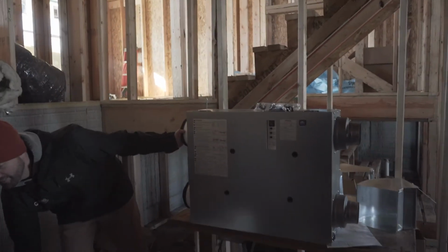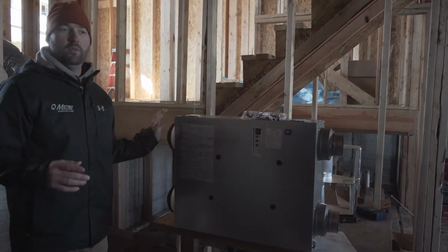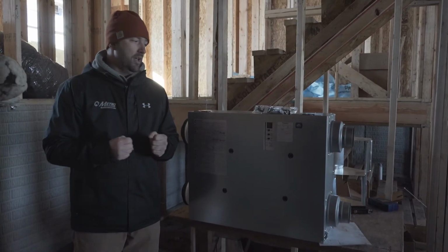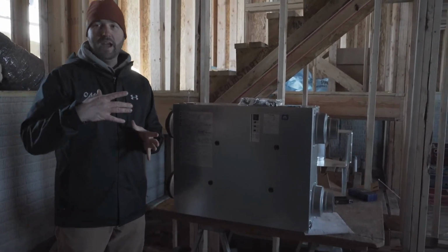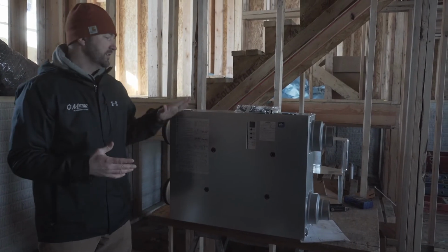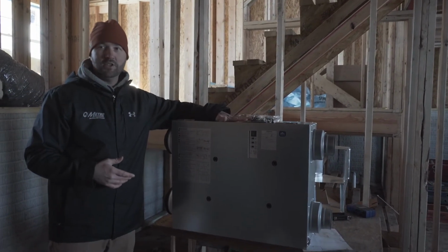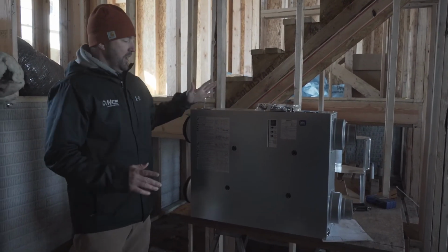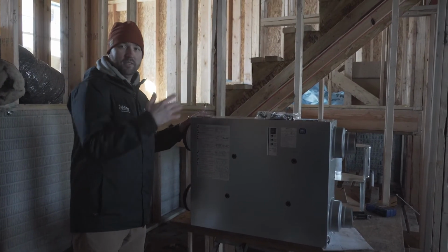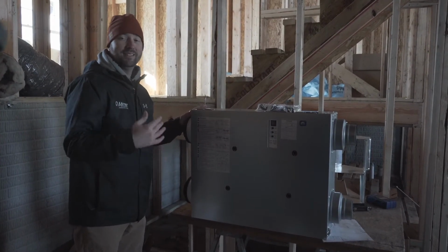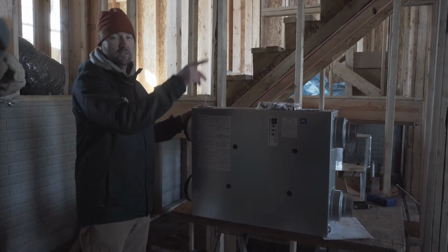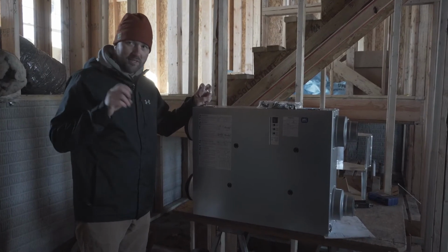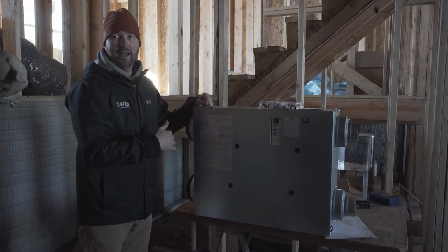So what we have here is a fresh air ventilator. In construction in today's day and age, they're building extremely, extremely tight. And so what's actually happening is your houses are pulling into a negative pressure. These aren't new to the industry, but they're newer to the industry within the past 10 to 15 years or so. What this does is it pulls in fresh air from outside, brings it inside your house, and exhausts the stale air outside your house. All your bathroom fans will hook up to this, and then it'll exhaust all the bad, moist air out of the house and bring in fresh air into the house.